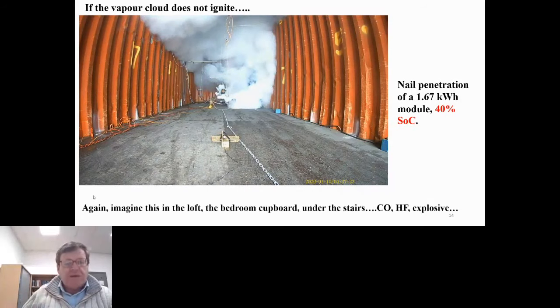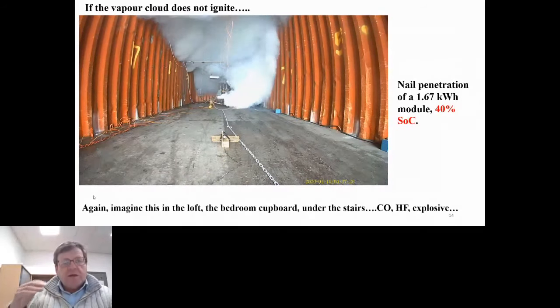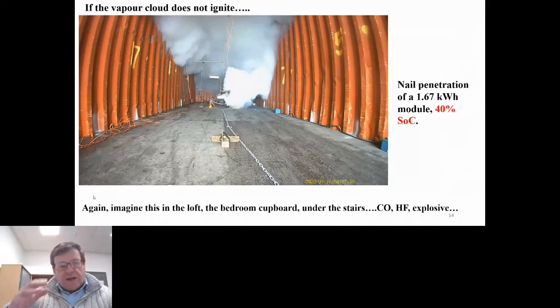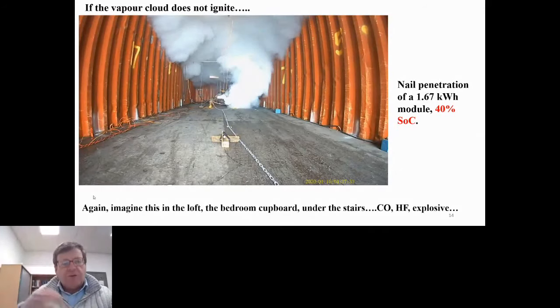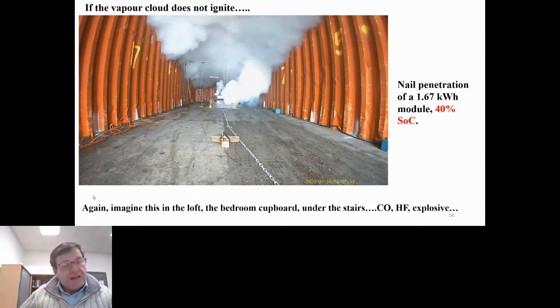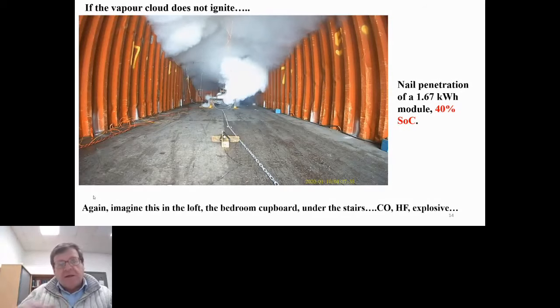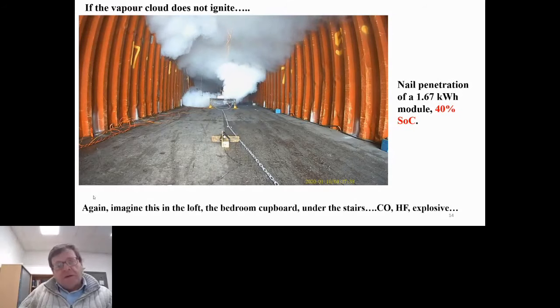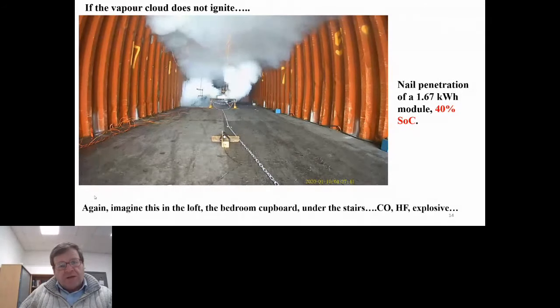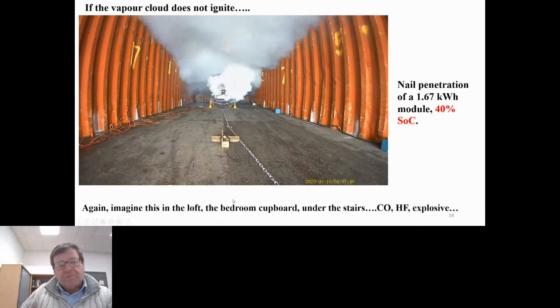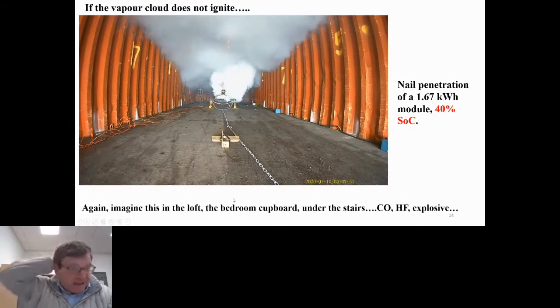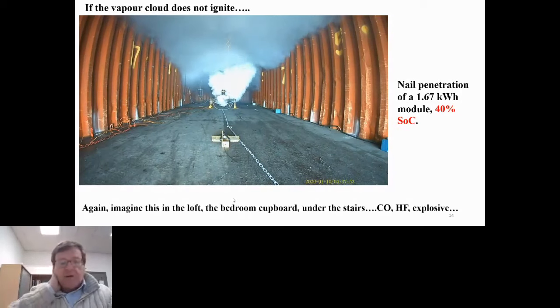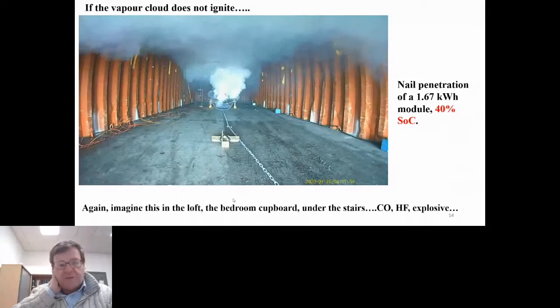You get a heavier than air vapor and a lighter than air vapor. We're not quite sure what regulates the relative amounts of these two, but we think it's something to do with, for example, the chemistry of the lithium battery. Again, imagine that in the loft, under the stairs, or whatever. And after a few seconds, we actually start seeing the heavier than air vapor that comes off, which creeps across the floor. We were actually trying to detonate this to create a vapor cloud explosion, but we were below the lower explosion limit, as it turns out, which is between 6 and 11%.